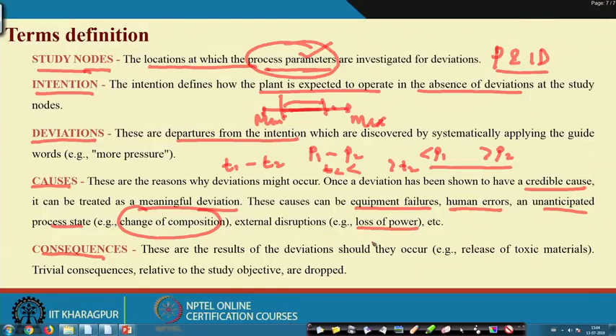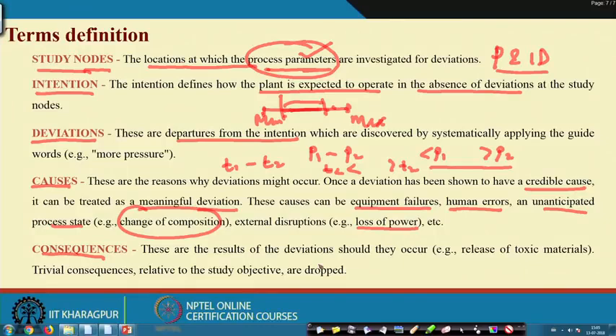Consequence is the result of the deviation. Once there is a deviation, for example over-pressure, what happens? The system reacts against over-pressure. There are relief valves, discharge valves, pressure gauge alarms, and all those things. Under an over-pressure situation the relief valve should work - it releases a certain amount of gas with reference to the pressure tank system - but if that fails, ultimately you have to think what will happen next. Due to the over-pressure situation, tank rupture will take place, with release of toxic materials. Trivial consequences related to study objectives are dropped.